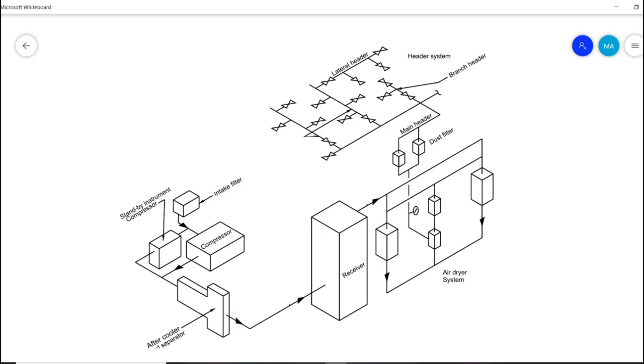This is the instrument air compressor detailed view. Let's quickly go through the different types of equipment. The system starts with an intake filter that filters atmospheric air into the compressor suction. After compression, the air goes into the cooler system, then into the receiver where compressed instrument air is stored. From there it goes into the air dryer system which removes moisture, and finally into the main header through dust filters, resulting in high-quality, moisture-free and dust-free instrument air.